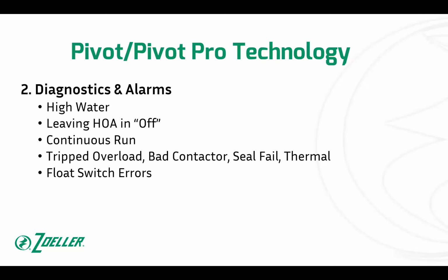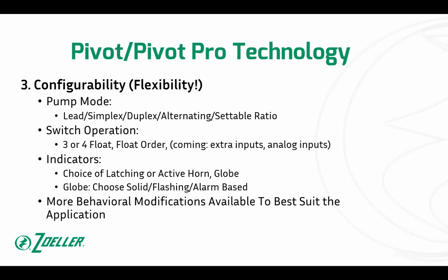But I'll repeat, on a traditional panel that we've all sold for many, many years, if that $30 or whatever a float costs, if the stop float gets stuck, the entire station will not run a pump. So it's just kind of an unfortunate but very real situation. Yeah, it's pretty wild.